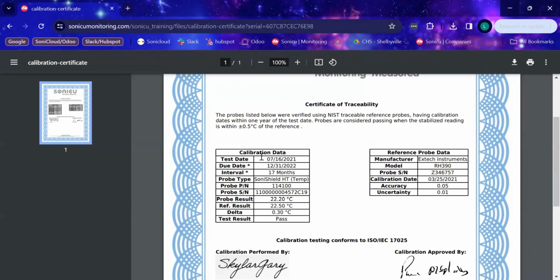It gives you that same information here: the date it was calibrated, the date it expires, how many months it was calibrated for, the type of sensor, the serial number, and down here where it says test result. We don't send anything into the field unless it passes testing at 100%.